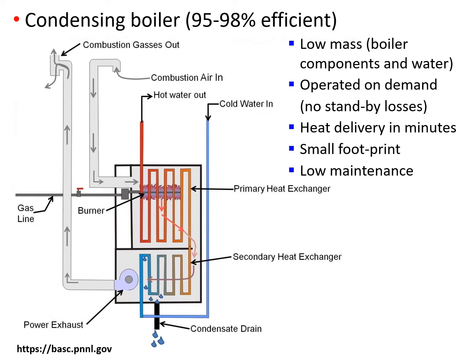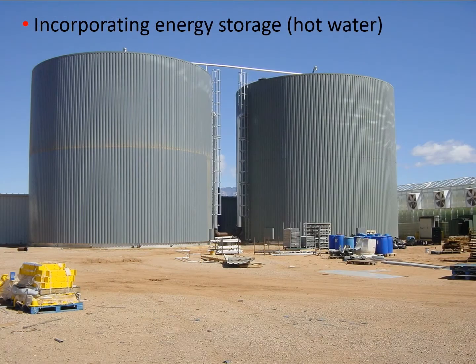It can be beneficial to store warm water as part of the greenhouse heating system. Having this capability can increase overall system efficiency because the boilers can operate at optimum efficiency for longer periods of time. These systems can also deliver instantaneous heat energy when it is needed.